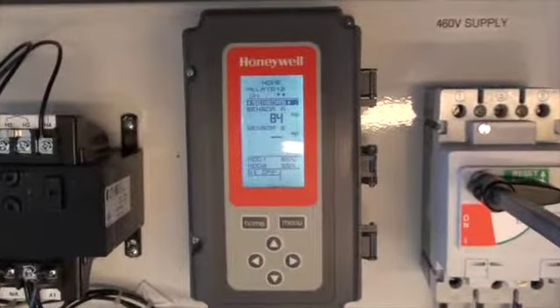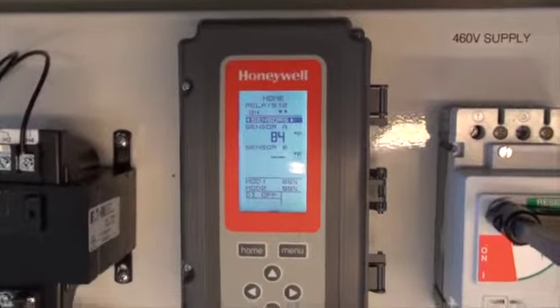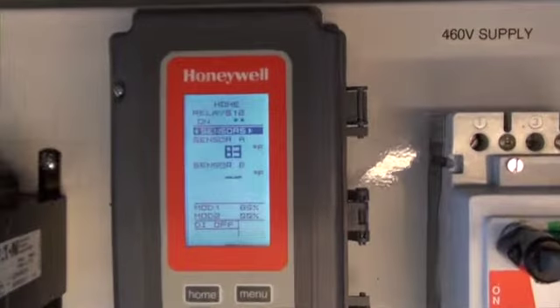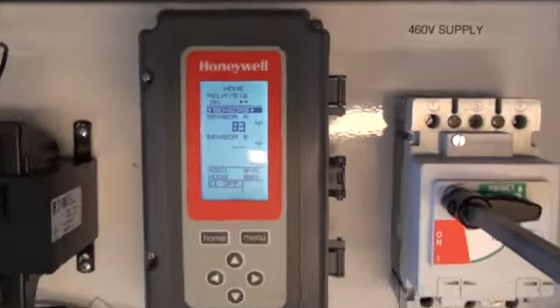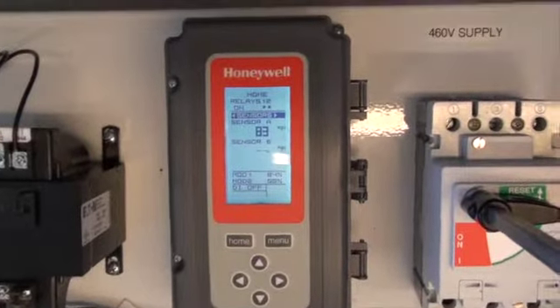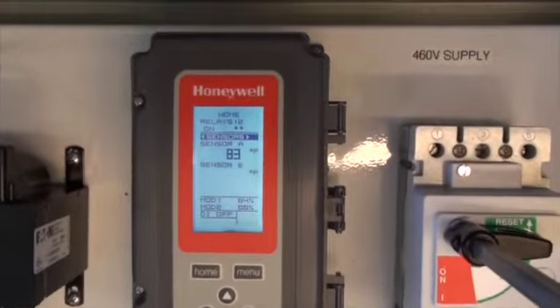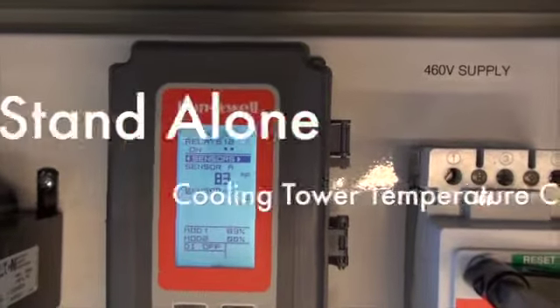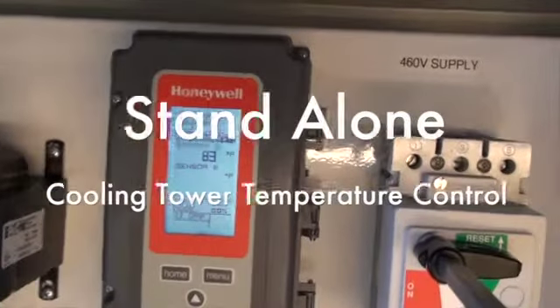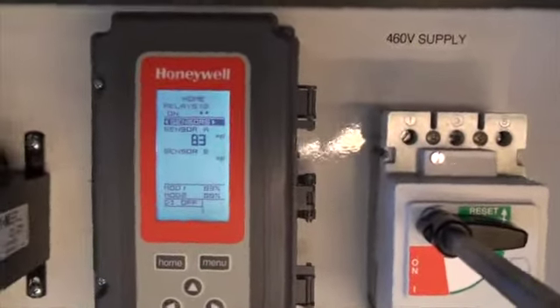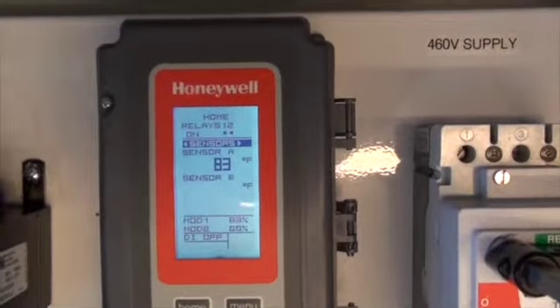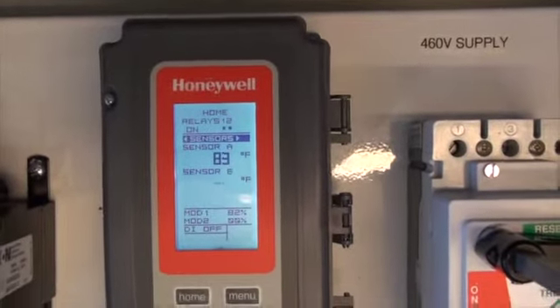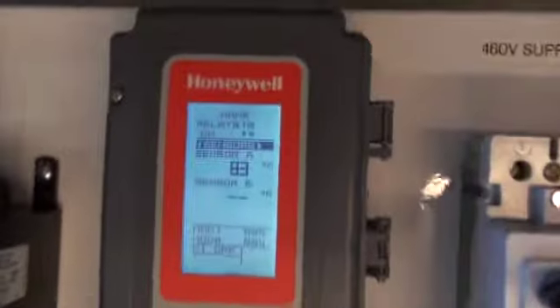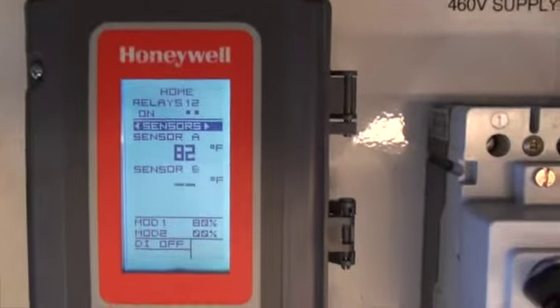Okay, here is the Honeywell T775 controller, and it's really an awesome controller for cooling tower applications because it can do so much. You can program up to 2 modulating outputs. It's got 2 to 4 relays. This one particular model has 2 relays, one for the spray pump and one for the tower fan enable. And it's got the modulating output to ramp the drive up and down and maintain process temperature.